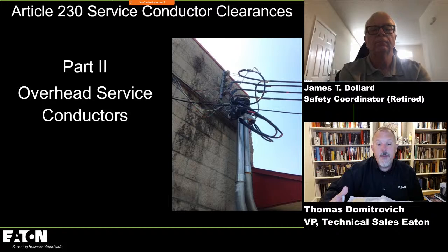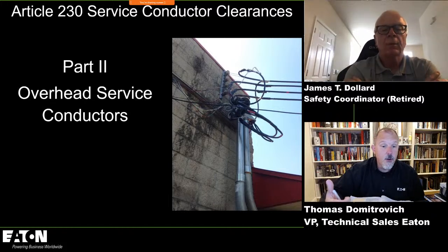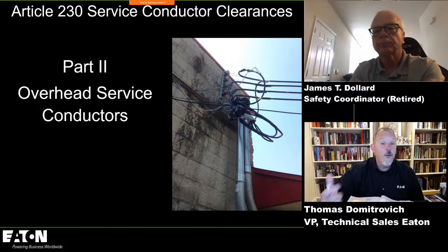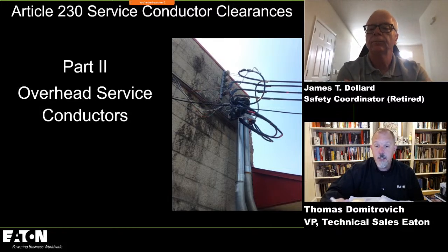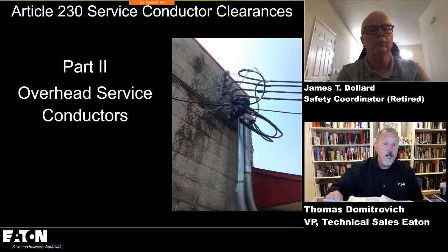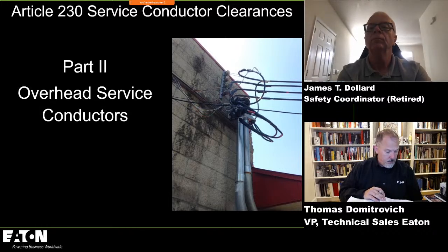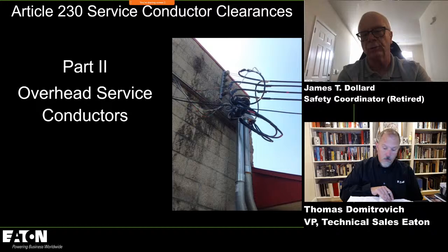And another thing about barriers, so distance, and we see in Article 230 Part 2 talks about overhead service conductors, and you'll find various requirements in 230, especially in Part 2, that talk about how far away it needs to be from the building, how high it needs to be. Those need to be off of the street, etc. And all that's about shock, right? Yeah, we don't want people reaching out a window or a fire escape, et cetera, and hanging their laundry on service entrance conductors. Now, do you hang your laundry outside the window?